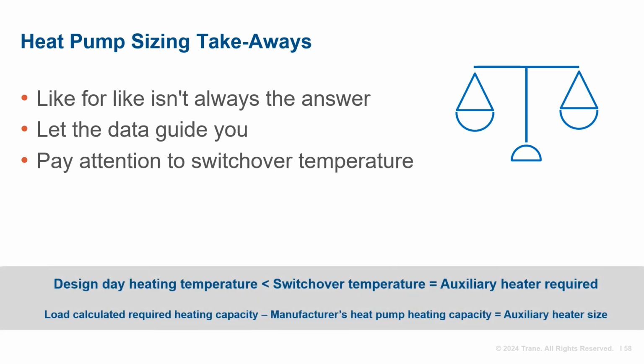If design day heating temperature is below the switchover temperature, then take the required heating capacity from your load calculation and subtract the heat pump heating capacity in the manufacturer's table or software, and size the auxiliary heater to handle the difference. And the same process would apply for sizing a dual fuel unit. As for dual fuel, though, check with your manufacturer's sequence of operation to know if the gas heat will run simultaneous to the heat pump heating operation. For these units, the heater should be designed based upon total heat loss.